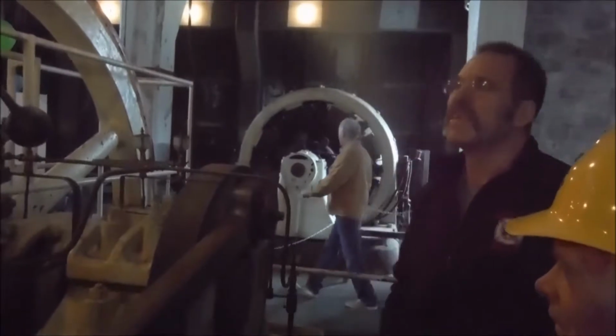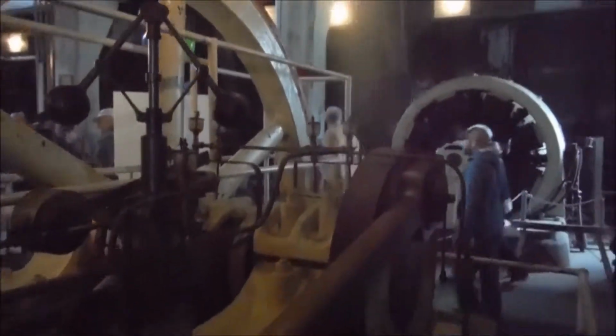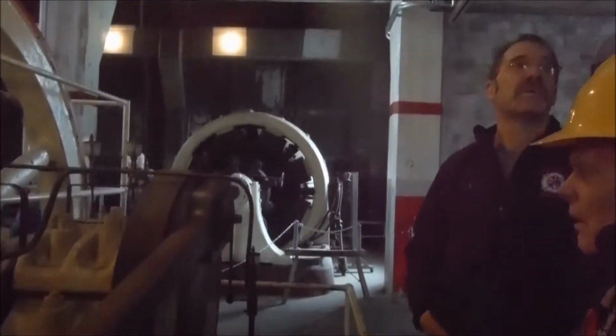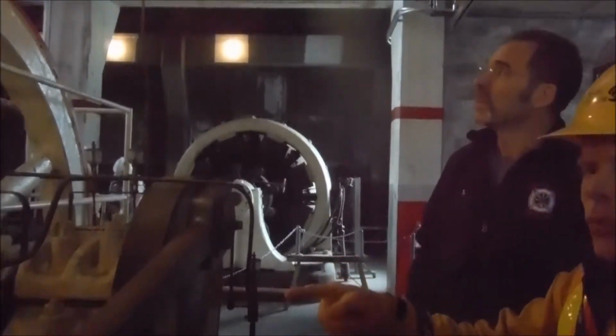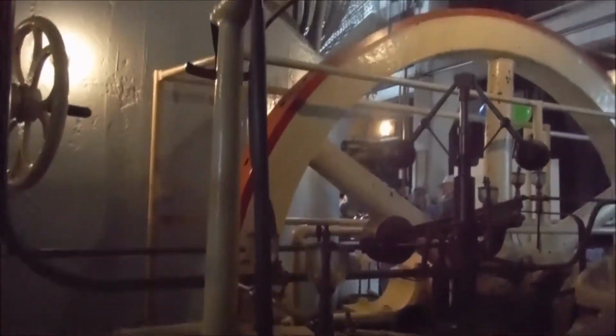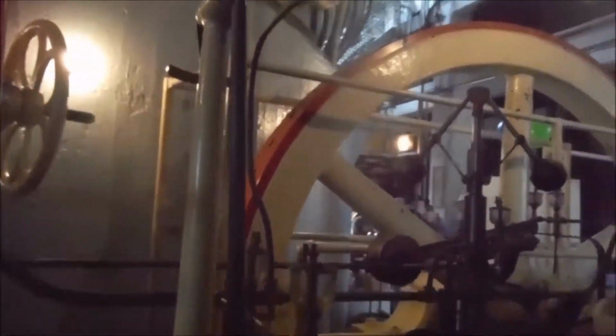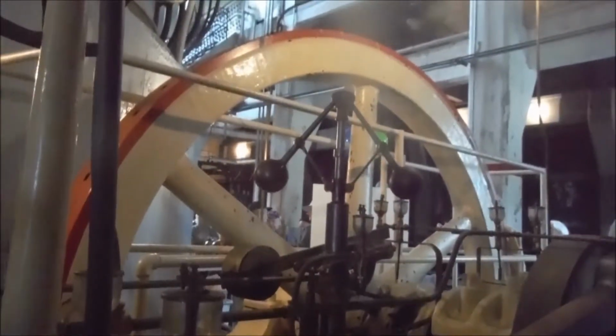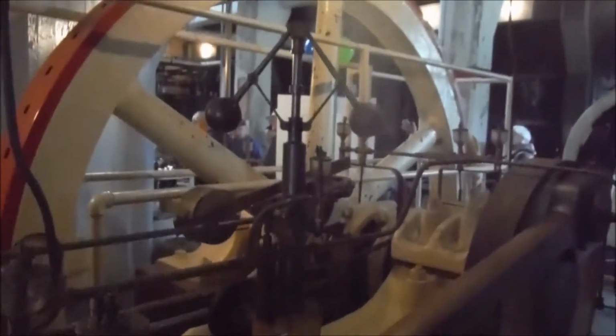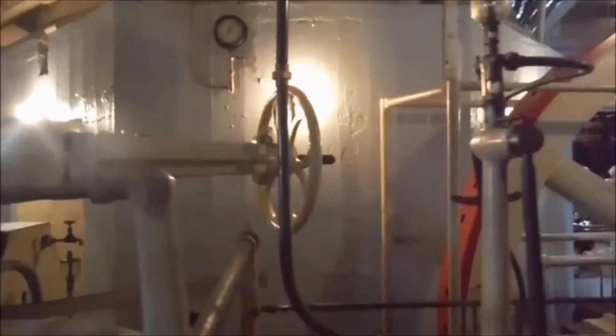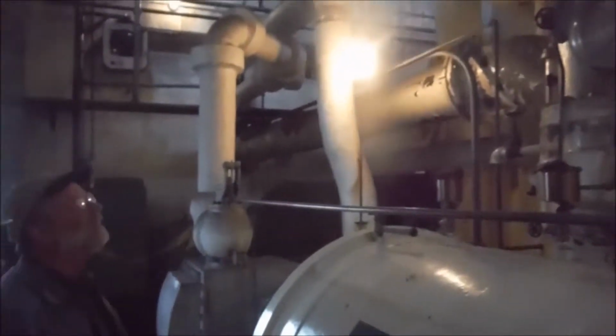And then you have another eccentric which goes to the valve on the pumping cylinder, switching ports so that no matter which way the piston is going, you're always pulling air out and shoving it back into the condenser, drawing it back in both ways.